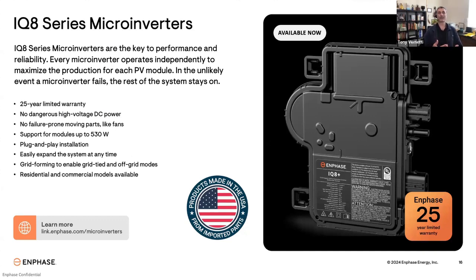The IQ8 series microinverter is the key component of the Enphase energy system. It not only maximizes energy production, it's also critical for our backup power systems because it has what we call grid forming capability. There are 5 models of the IQ8 series microinverters with different power ratings, as Kyle pointed out, so it makes it easy to find the perfect pairing for their solar module of choice. The highest power model we have is the IQ8HC, which is suitable for modules up to around 530 watts.